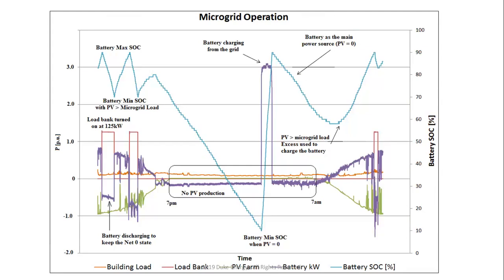I showed you how we do the island. I'm going to show you later on how we do resync. So when we reach 10%, the system automatically resyncs. We charge the battery from the grid. We get to about 90%. You can see that takes about an hour and a half, depending on the demand. And then, again, battery is the main source. So somewhere around 3 or 4 o'clock in the morning, battery again disconnects automatically from the grid and becomes again the main source of voltage and frequency, main power source. So it goes down, right? When it gets down to about 60%, around 7 or 8 a.m., the green line, which is PV, becomes higher than the orange line, and then we start charging the battery, right?